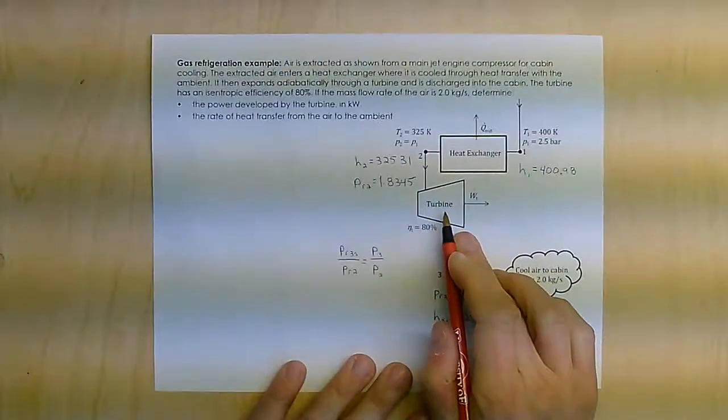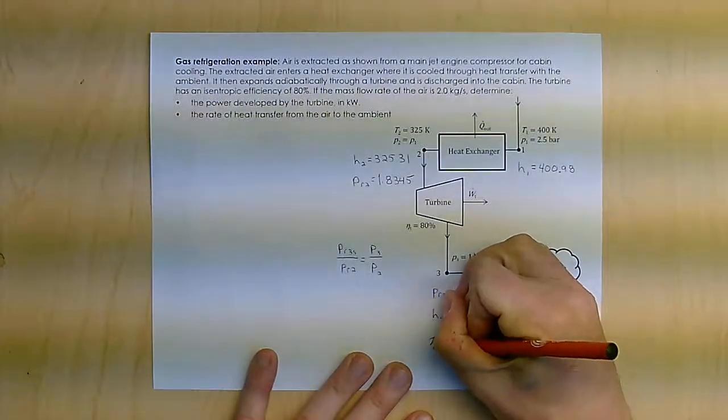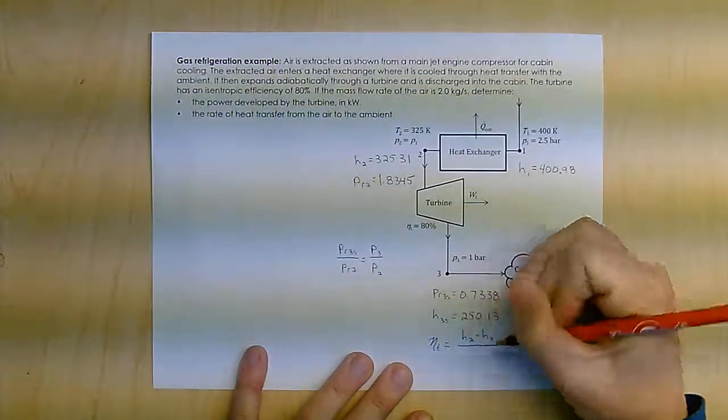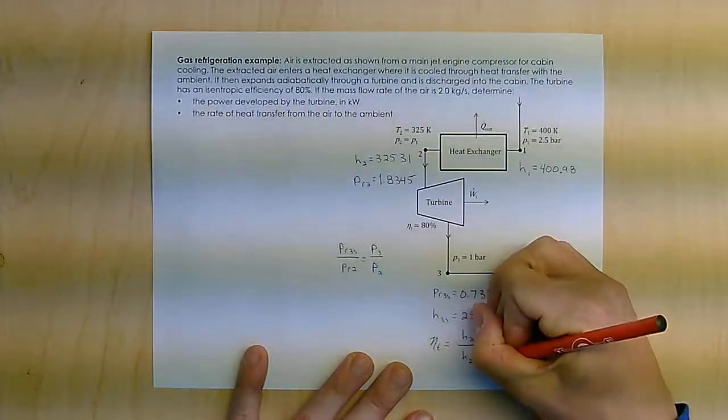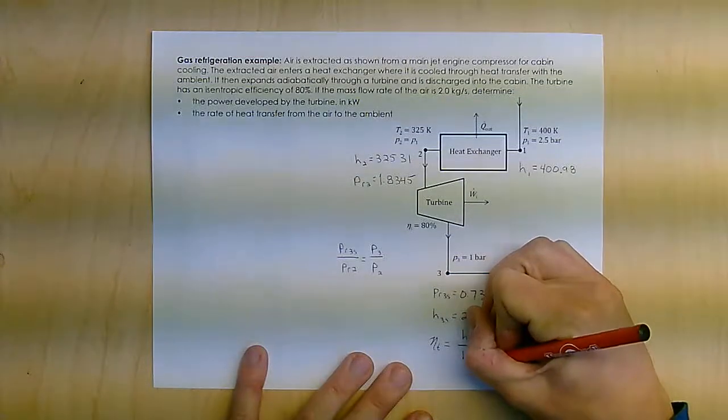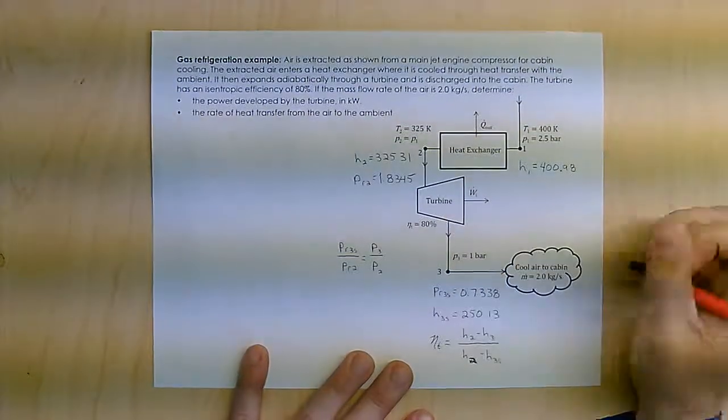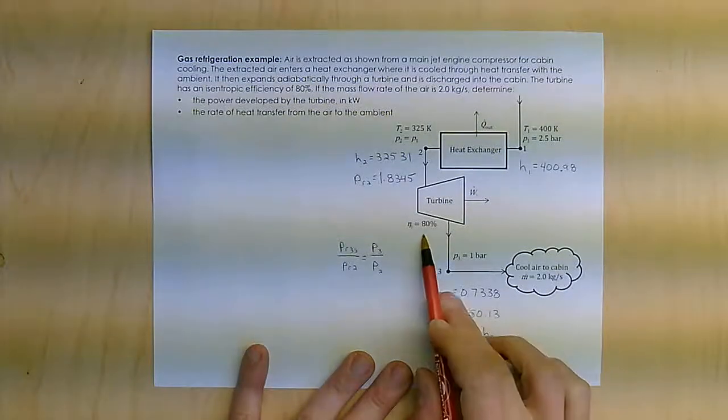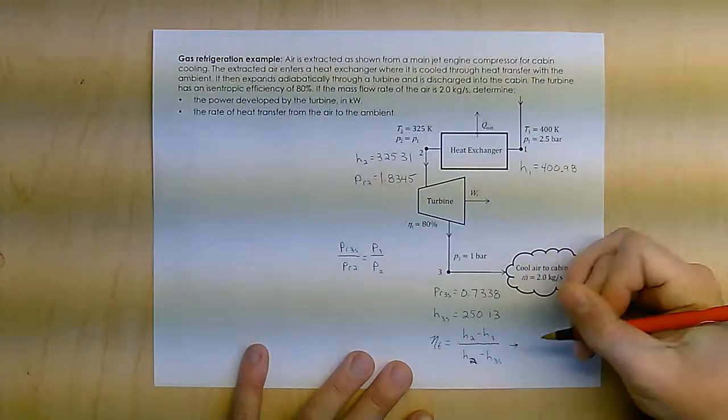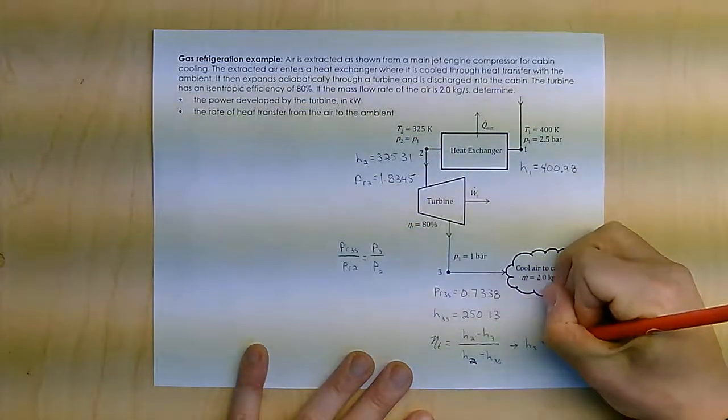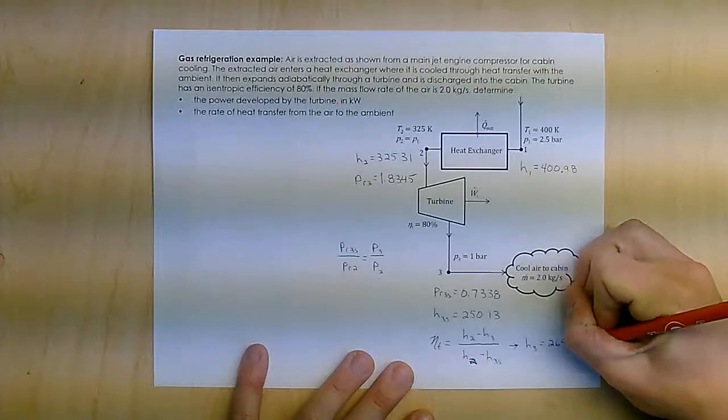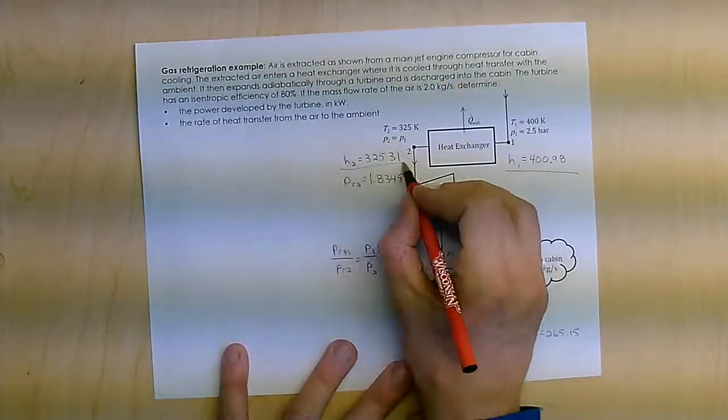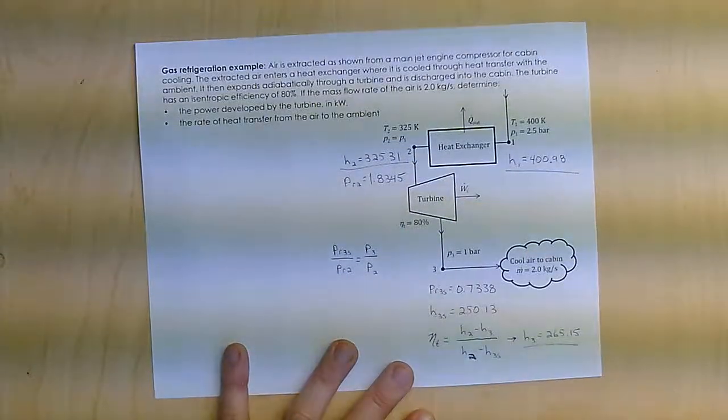Then the fact that I know my turbine efficiency is 80%, so I know that my turbine efficiency is defined as H2 minus H3, the actual performance of the turbine over the ideal performance of the turbine. This is 80%. From this, I can calculate that the actual H3 is 265.15. So now I've set H1, H2, and H3.